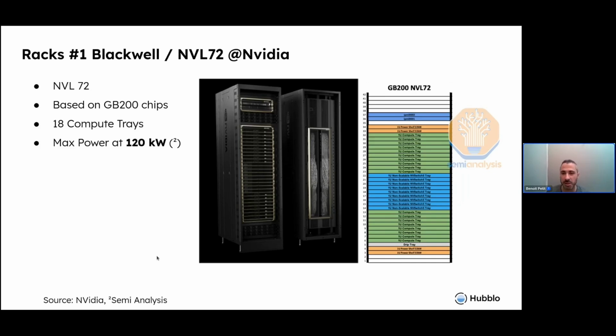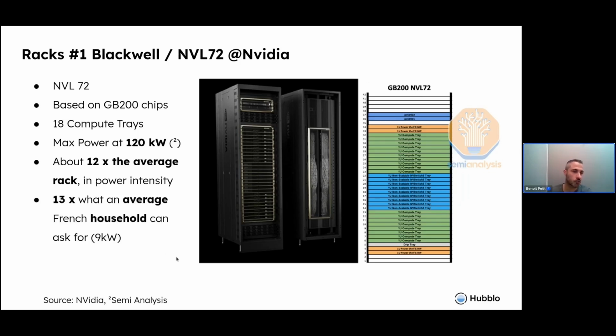And the maximum power of this rack is about 120 kilowatts. So you see the difference with the average rack power we had before. It's about 12 times the average rack that we might have now if we consider that we are around 10 kilowatt per rack. And to compare that to something more outside of IT, it's about 13 times what an average French household can ask for in terms of power, because in most households, if you ask for more than 9 kilowatts of power, then your electricity counter will just shut down the line. Those are already pretty huge values for a single rack.